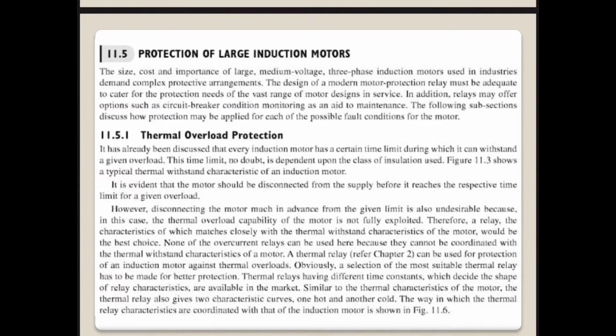But large induction motors, which are medium voltage three-phase induction motors used in industries, require complex protective arrangements. These may give additional options such as circuit breaker condition monitoring, which is an aid to maintenance. So now we'll see thermal overload protection. We'll see different protections against under voltage, stalling, and reverse phase sequence, the things which we have studied. The first one is thermal overload protection.